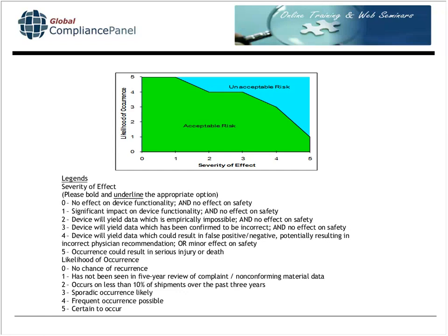Also, any point that falls exactly on the division line, for example, a severity 2, likelihood 4, is considered to be acceptable risk. A point must be completely contained in the unacceptable risk area to be an unacceptable risk, which again requires some sort of field action.